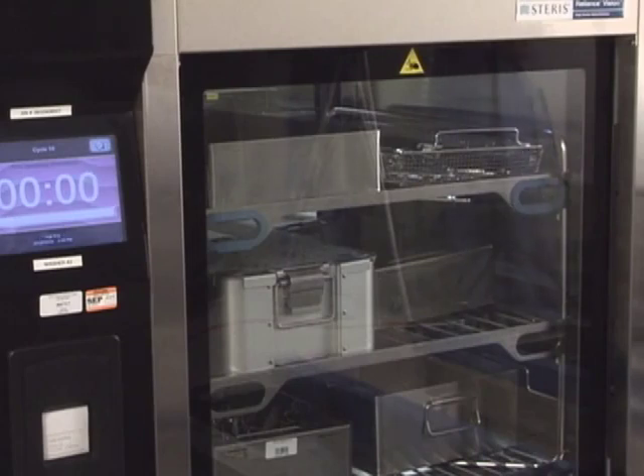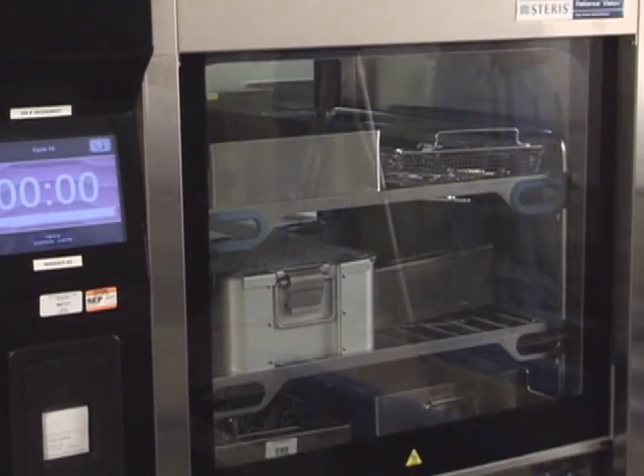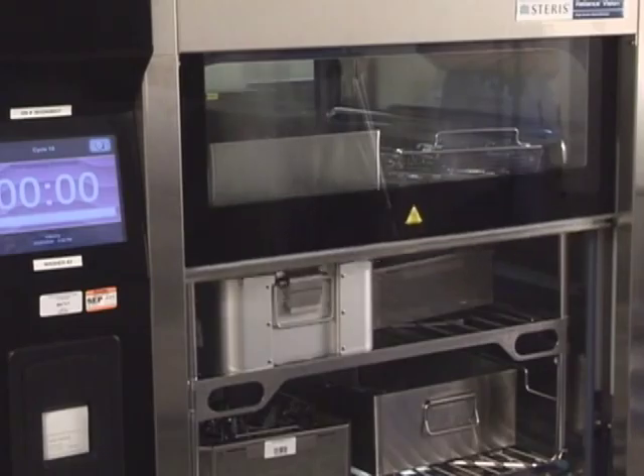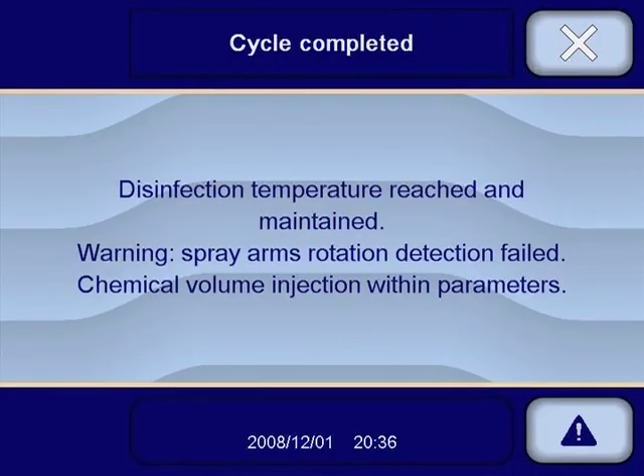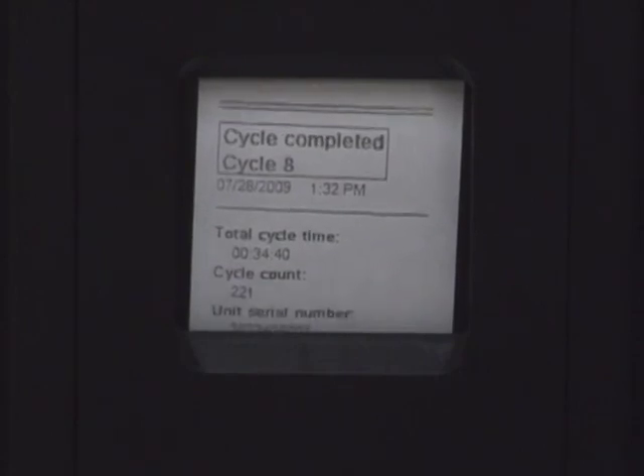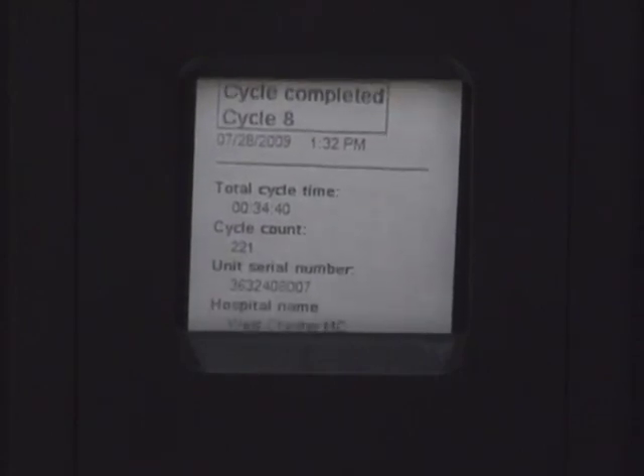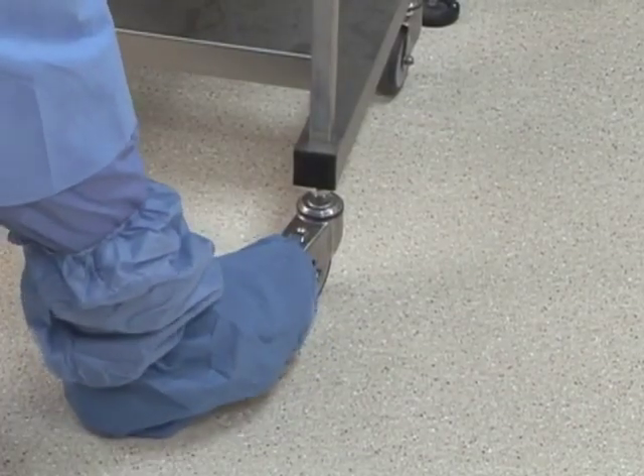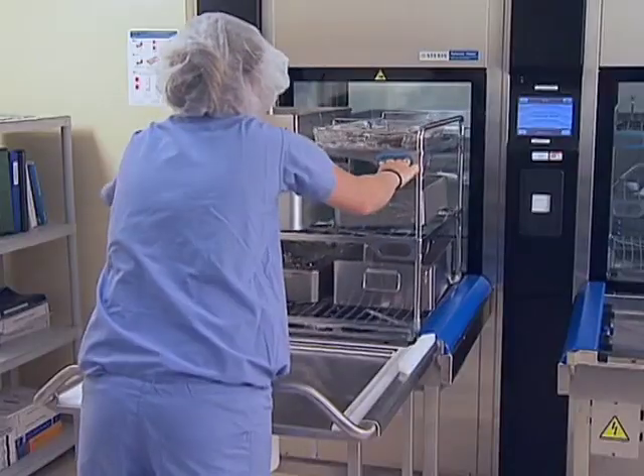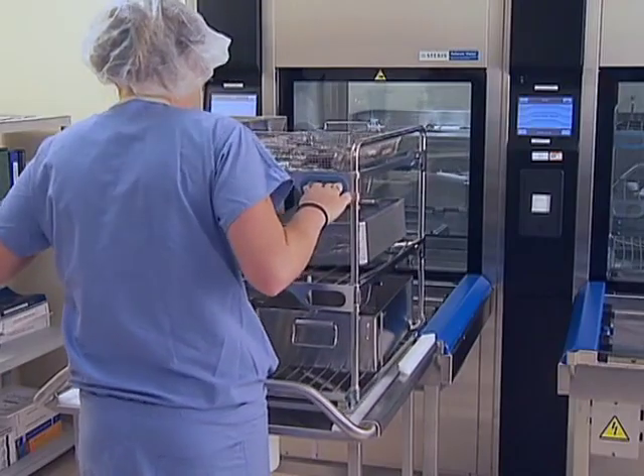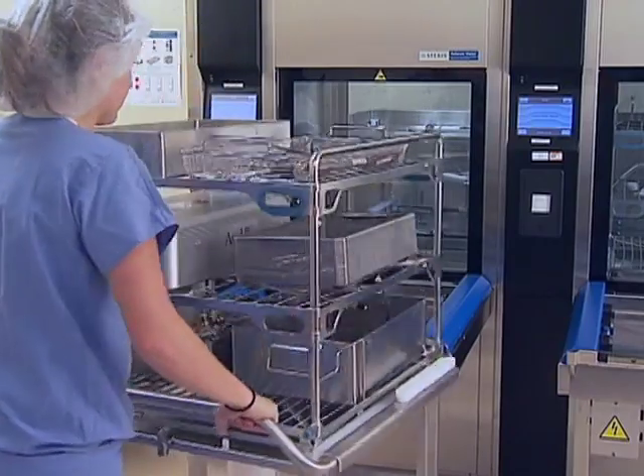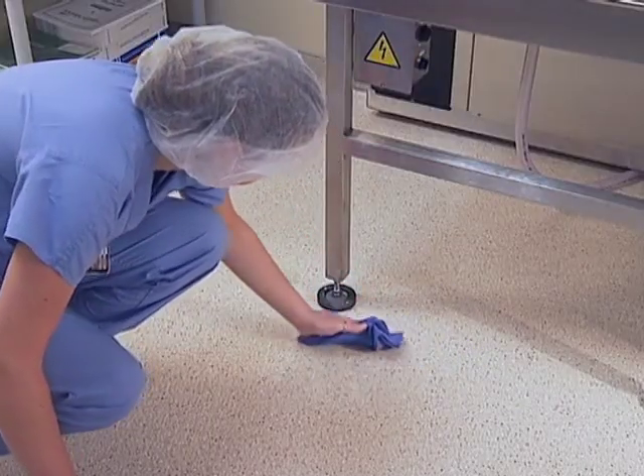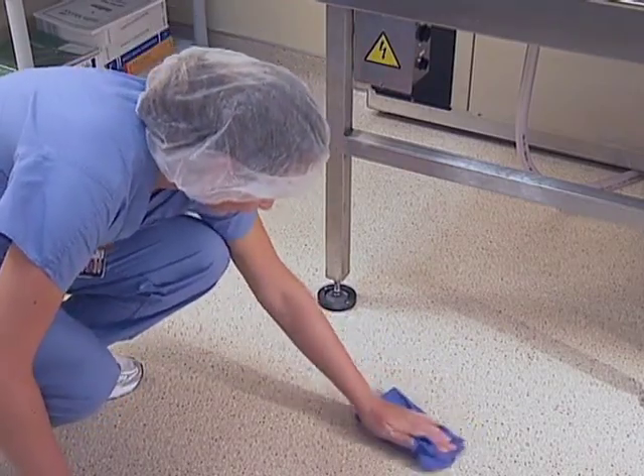Once the cycle is finished, a signal sounds and the chamber door on the unload side opens. The PC control screen displays the cycle completed screen. A detailed printout is generated to document the cycle, including any warnings or alarms that occurred. Lock the transfer cart into place and carefully unload the rack from the chamber onto the cart. Be sure to clean up any water spills to prevent injury.